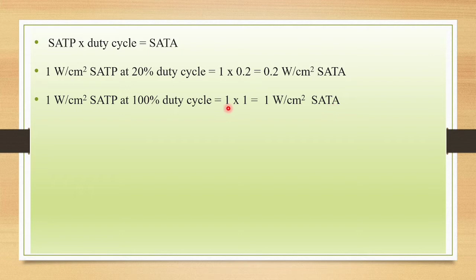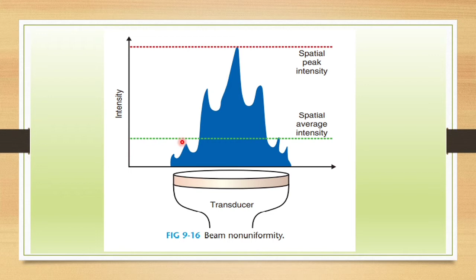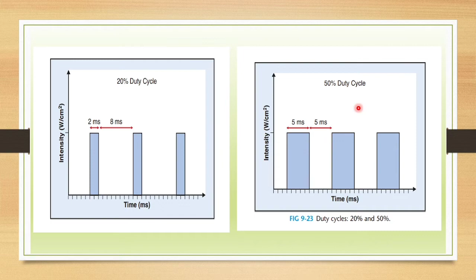So this is the same diagram, spatial peak intensity and spatial average intensity. Spatial peak intensity will be higher at the center and lesser as it travels towards the edges of the ultrasound beam. And this is the diagrammatic representation of the duty cycle. These are two duty cycles for pulsed ultrasound. So 2 milliseconds of on period and 8 milliseconds of rest period is known as 20% duty cycle, and 50% duty cycle means 5 milliseconds of ultrasound on period and 5 milliseconds of off period. So the ratio of on and off period is known as your duty cycle.